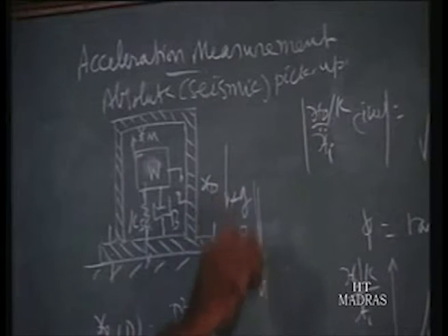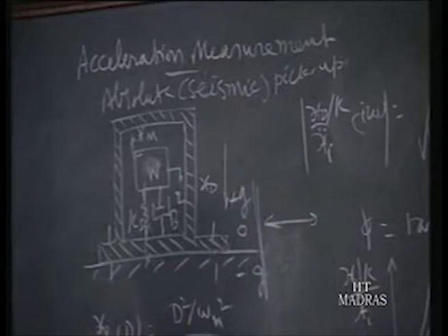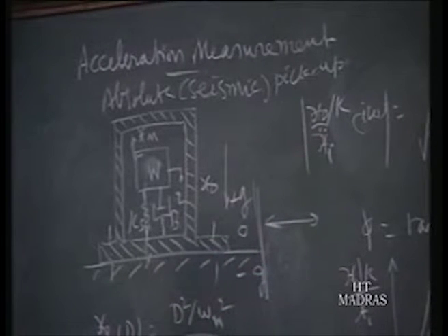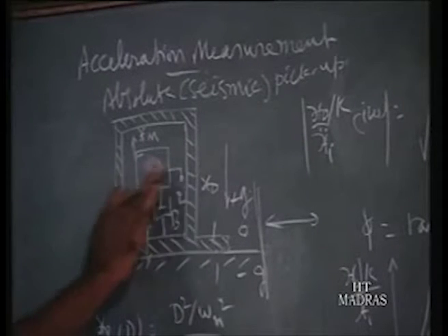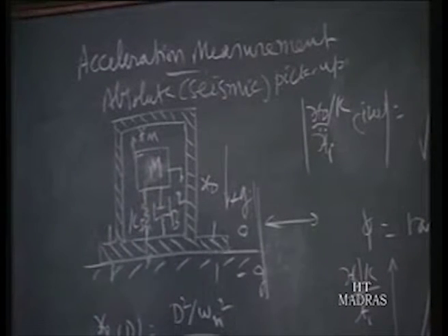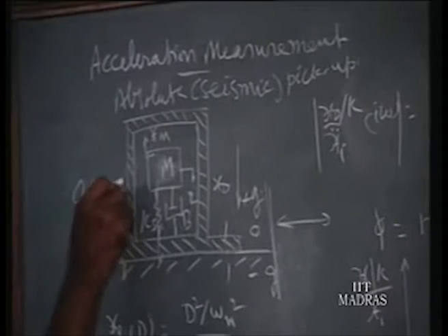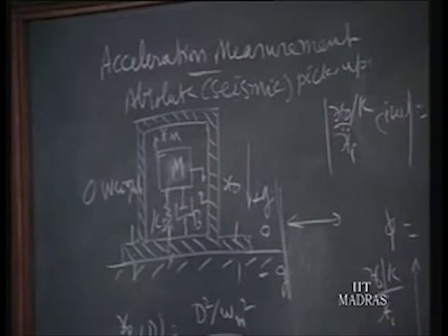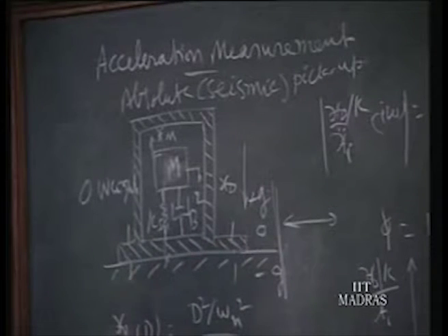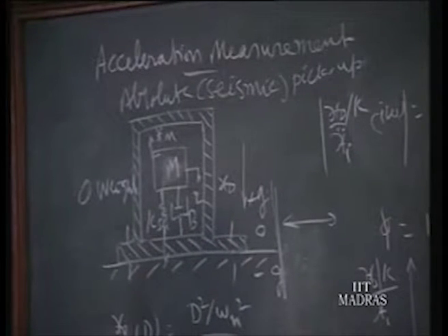So this calibration is mainly meant for horizontal motion. When the motion takes place horizontally, perpendicular to the G direction, the calibration is valid. It is because for vertical motion you have to be careful. In case it falls freely down, what will happen? What is the weight of the mass? Any freely falling body has zero weight. So when it is falling freely, acceleration is G, but what is shown is 0. So for vertically downward motion, whatever the instrument shows, you have to add 1 G. You have to be careful.